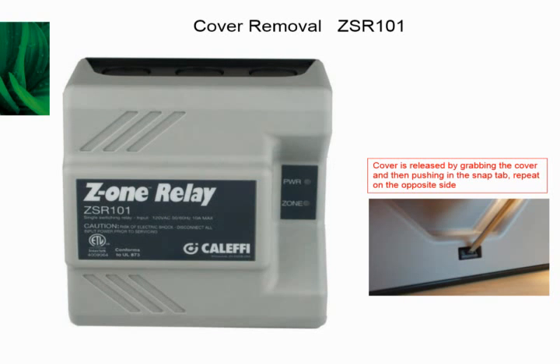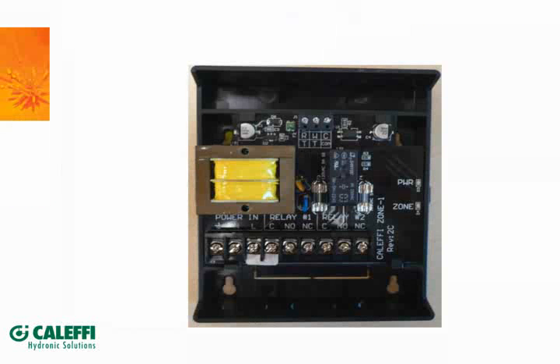And then I think, Mike, you talked about how it has to do with the listing on it. You can't make it that, it has to be a tool to remove it, or the listing is different and changes. So it's not trying to make it hard. Correct, but that's part of the requirement. The UL standard requires that a tool be used to remove the cover. Yep.